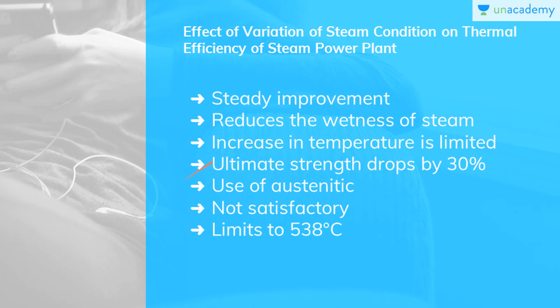However, the increase in steam temperature is limited by the properties of the construction materials of boilers and turbines. The ultimate strength of unalloyed steel drops by about 30% as the steam temperature rises from 400 to 500 degrees centigrade. Alloying with chromium and molybdenum and also by the use of austenitic instead of ferritic steels increases the strength at high temperatures.